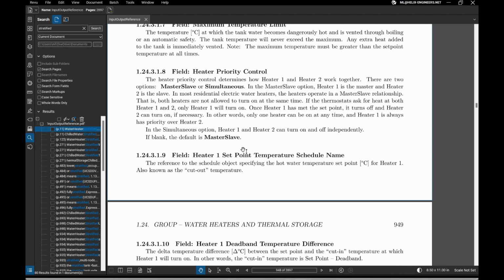If we take a look at the input-output reference manual, basically what this is saying is it has to do with the top heater number 1 and the bottom heater number 2, and whether these will operate together or whether they operate separately. So master slave, heater 1 turns on only, and then heater 2 turns on later after heater 1 turns off. Or simultaneous means that they heat at the same time.